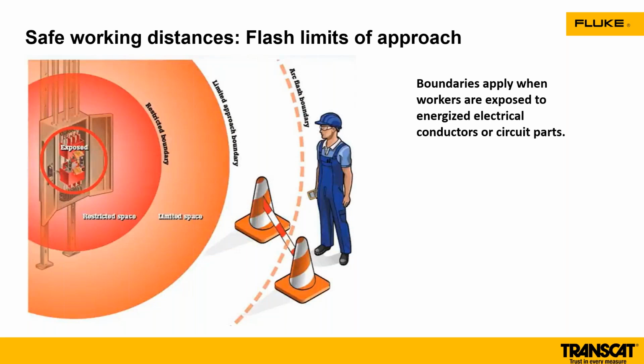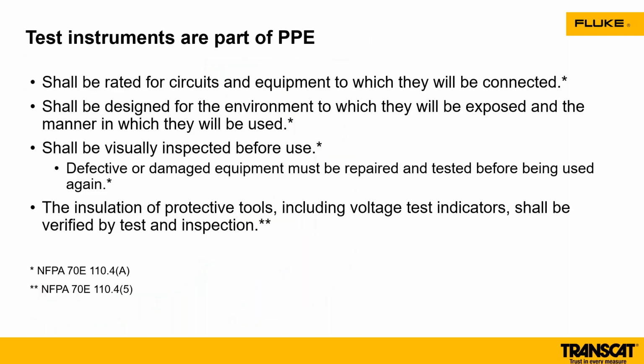I again highly recommend that you go out and look at it and start learning how to do those load studies on your approach boundaries, your limited approach boundary, and your restricted area spaces. As I mentioned, the test instruments are part of your PPE. They need to be rated for the circuits and the equipment that you're going to be connected to. They need to be designed for those environments which may be exposed in this manner, and where you're going to be used. You need to inspect your equipment daily, if not weekly, but daily.